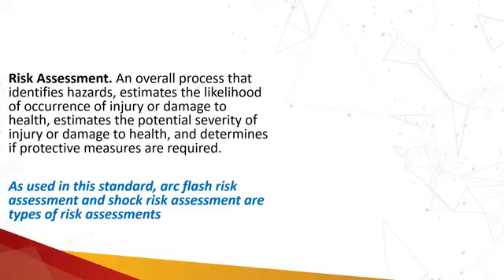So whenever in 70E you are going to hear the words risk assessment, you have to categorize those risk assessments into the shock risk assessment and arc flash risk assessment. There will be some situations in which the shock hazard is present, but the arc flash hazard is not present. There will be situations in which the arc flash hazard is present, but the shock hazard is not present. There will be situations in which both are present, and the fourth situation will be in which both are not present. How those situations or scenarios will be developed, we will discuss shortly.